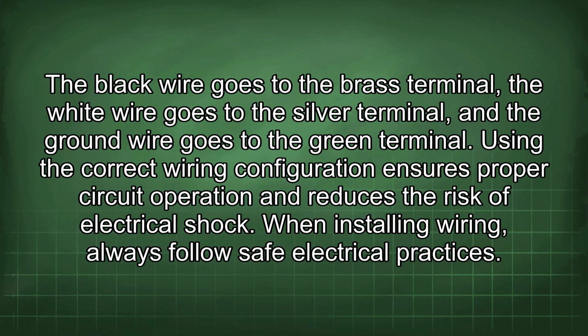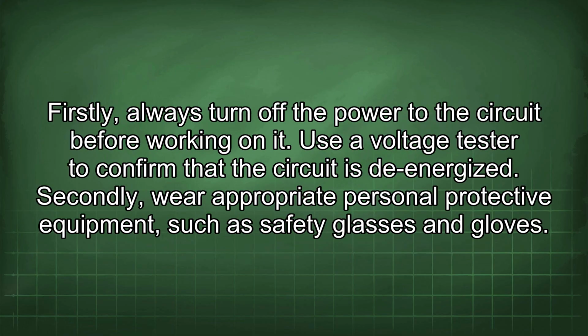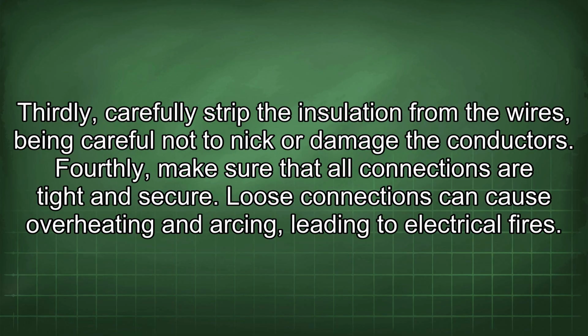When installing wiring, always follow safe electrical practices. Firstly, always turn off the power to the circuit before working on it. Use a voltage tester to confirm that the circuit is de-energized. Secondly, wear appropriate personal protective equipment, such as safety glasses and gloves. Thirdly, carefully strip the insulation from the wires, being careful not to nick or damage the conductors. Fourthly, make sure that all connections are tight and secure. Loose connections can cause overheating and arcing, leading to electrical fires.